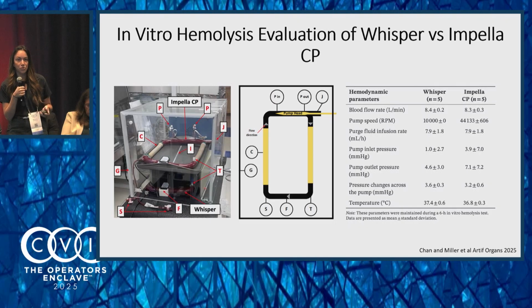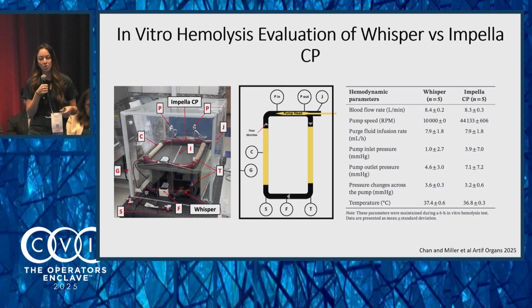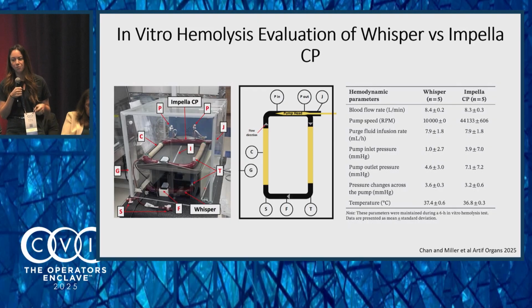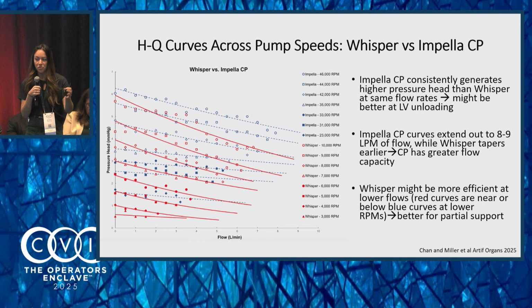This was an in vitro hemolysis study. They designed two circuits, put the pump in, then compared it to the same circuit with an Impella CP pump, and filled the circuit with cow blood. Then they ran the circuits at really high flow rates - the Whisper at 10,000 RPMs, producing a blood flow rate of about 8.5 liters per minute. Then they measured these HQ curves.